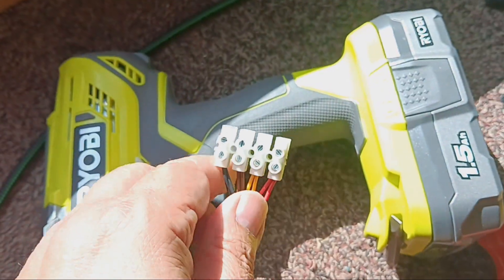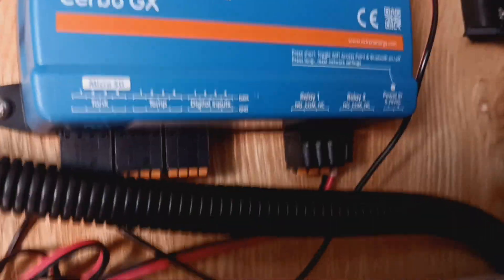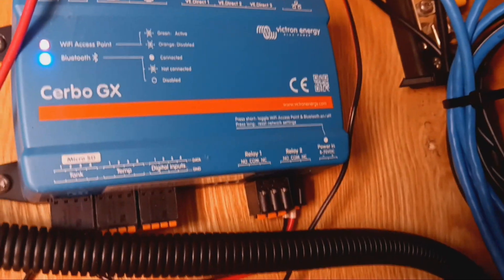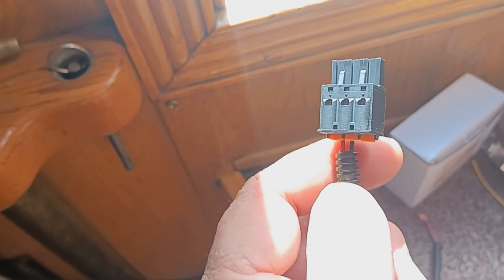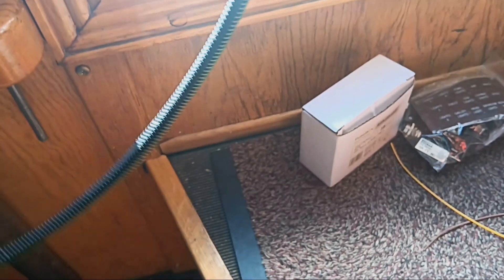To start up we just connect red and black, and it will fire up. This allows the Cerbo to work with it and also the timer to stay connected as well — I wanted the option of using both. On the Cerbo we've got pull-out connections which we can take off to connect up the cabling. Here you can see where the relays are — we use the common and normally-open on relay one, so we just pop the wires in and push it back into the Cerbo and connect those two wires up.